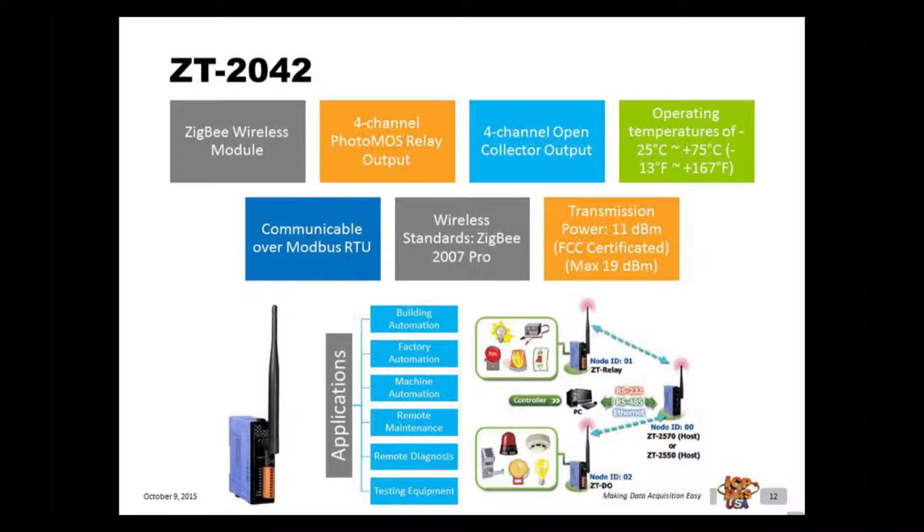The ZT2042 offers four photo MOS relay output channels and four sink type digital output channels with short circuit protection. Each channel features photo coupler isolation. The ZT2042 has eight LED indicators to display the digital output channel status. The ZT2042 can be used in many applications such as building automation, factory automation, machine automation, remote maintenance, remote diagnosis, and testing equipment. It can be connected with alarms, locks, smoke detectors, and other sensors for security alarm systems, and can interact with other Zigbee wireless data acquisition modules like the ZT2570 or ZT2550 for a wireless remote monitoring system.